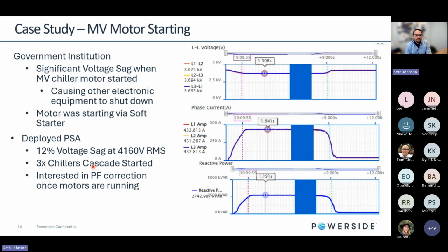We did this metering at 5 kV, but their point of common coupling was upstream at 13.8 kV. So we actually provided a report for both the 5 kV and the 13.8 kV side, so that they understood the implications of the motor starting and the voltage sags that we were seeing at 5 kV, but also upstream, at the utility point of common coupling connection point. So what they ended up seeing here was about a 12% voltage sag at 5 kV.